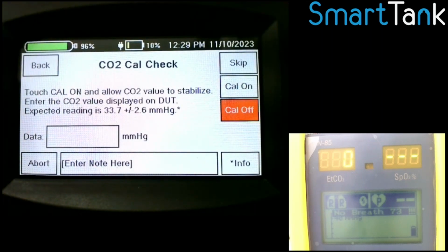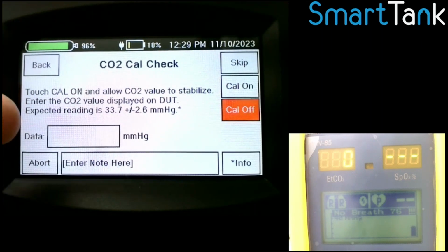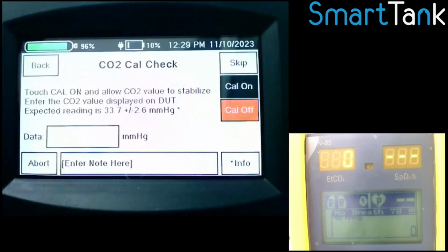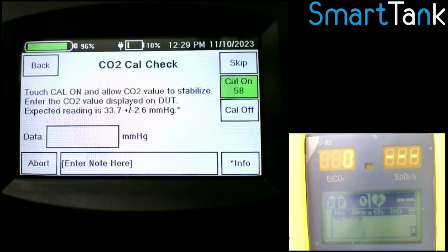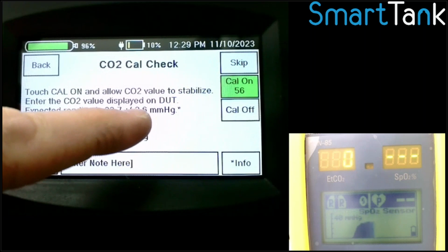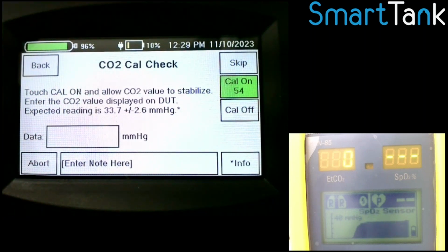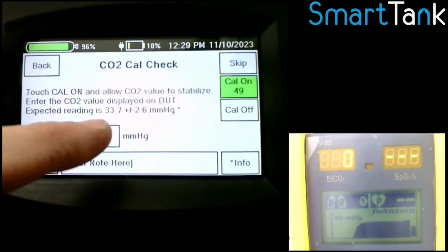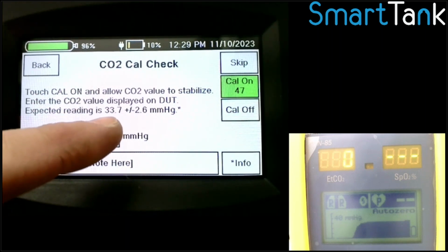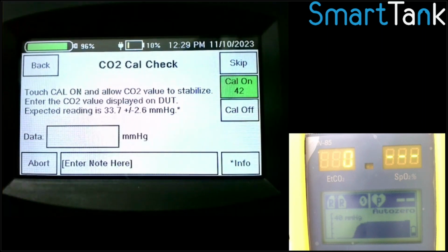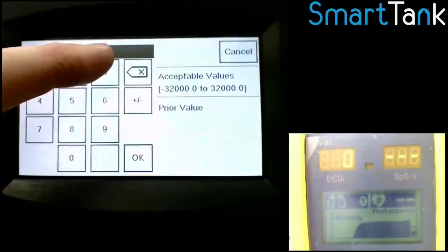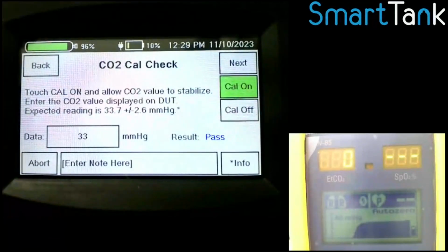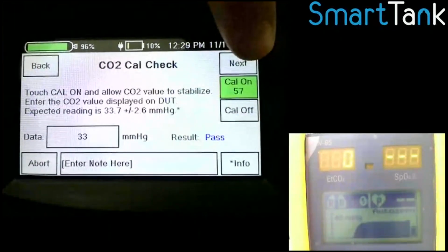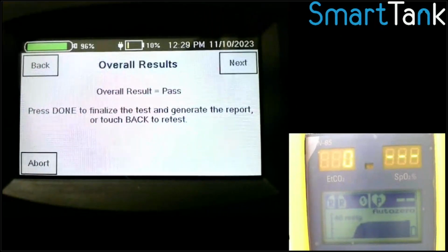So at this point, in theory, the device is calibrated, and now we want to do our calibration verification. It's asking you to go in, deliver gas again, and then to provide a value, this value that's going to be 33.7 millimeters of mercury. So historically, you would have had to do this calculation, take the 5% times the atmospheric pressure, but the SmartTank will just do that for you. It automatically calculates. It should be 33.7, and then the pass-fail criteria. And so we're just going to go ahead and say, yeah, that passes, because we just calibrated it. All of this will go in the test report. I'm going to hit next, and it'll automatically shut the gas off.